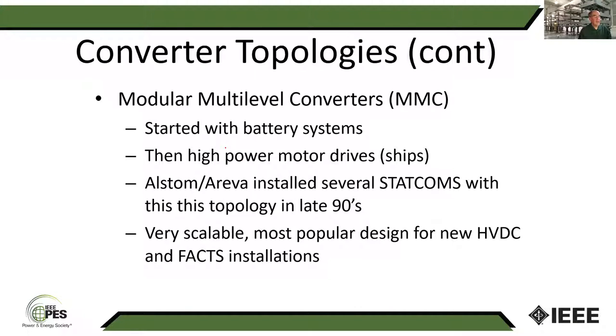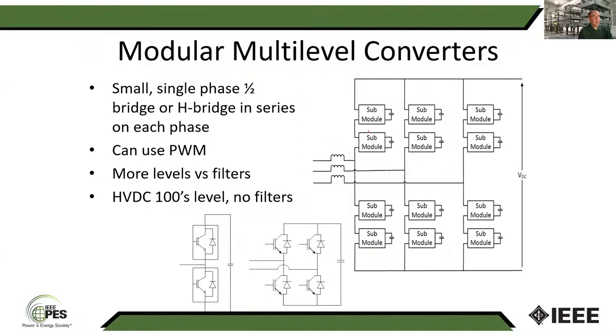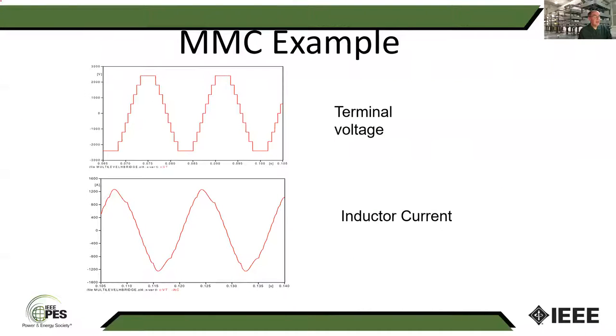Another variant is something called a modular multi-level converter. This was first developed for battery systems and then went on to high power motor drives for things like ships. And so now we've got a bunch of these submodules connected in series. For high voltage DC transmission, you may have 400 modules going from this leg to this leg. You don't see these as much at the voltage levels you'd see in a microgrid, but if it was connected to the transmission system, you could still see that. And so if you take something like this, now we get a waveform. Every time we switch a module, we just produce steps like this. That reduces the harmonics further, and it also reduces the switching losses. Once you get to about 16 levels, you can reduce the voltage and current harmonics to meet the IEEE 519 or the IEC 61000 limits for harmonics.